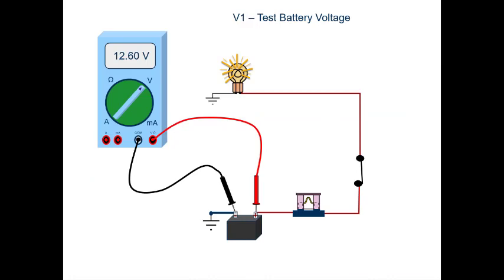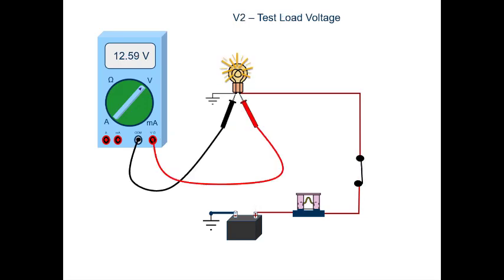In this example, we're displaying the V1 portion of the test, which tests for voltage at the power source. Confirming source voltage should be the first step in the V1 through V4 process. It does not matter if the load is on or off. In this example, we're displaying the V2 portion of the test, which tests for voltage at the load. In a functioning circuit, you should see the applied voltage, or maybe a tiny bit less to account for wire resistance. You should see this general voltage with or without the bulb in the socket.